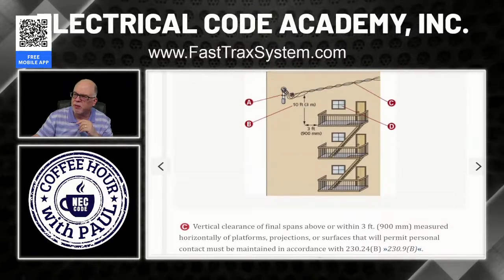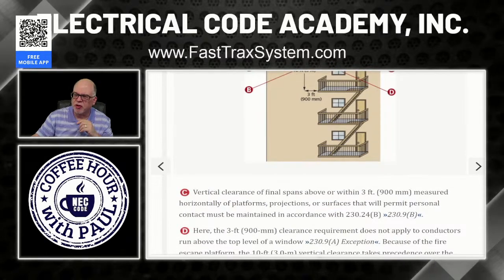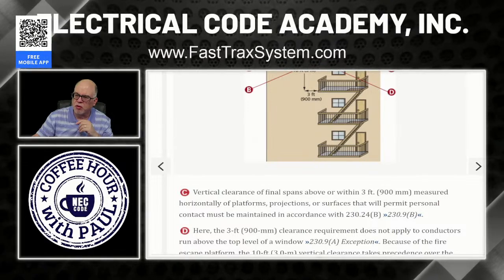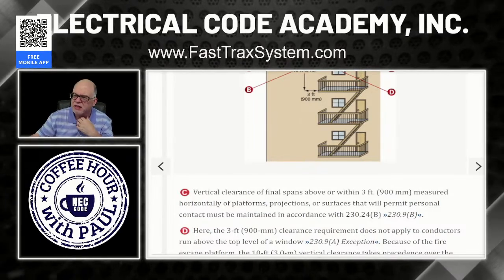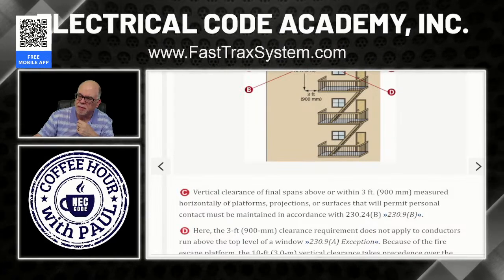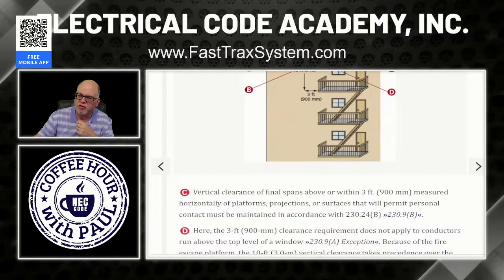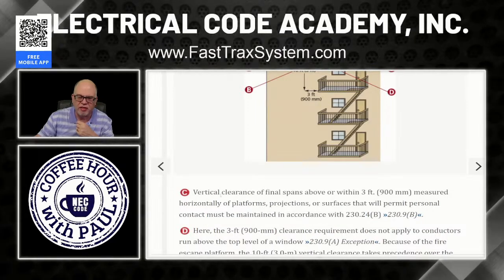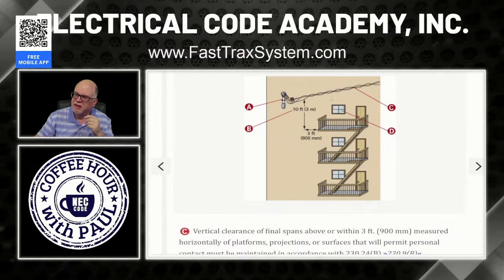Now, going down a little bit, here's the conductors right here. So they kind of drop over, right? All right, so vertical clearances, the final span above or within 3 feet measured horizontally of platforms. You saw that earlier, platforms, windows, doors, or whatever, okay? It says the vertical clearance and the final span above or within 3 feet measured horizontally of platforms, projections, or surfaces that will permit personal contact must be maintained in accordance with 230.24(B). And we saw that.